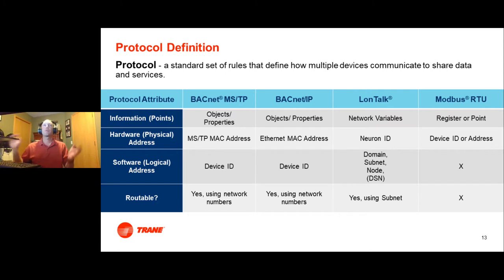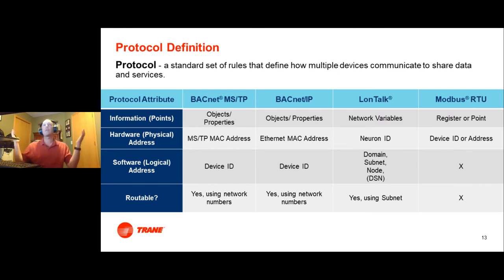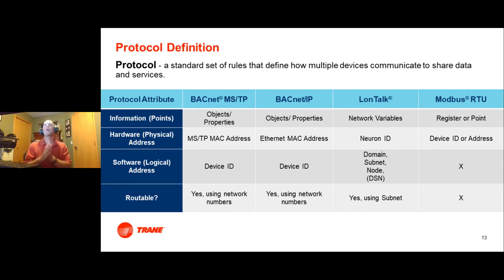A protocol, at a high level, is a way for two different controllers to communicate — hopefully between different vendors to help build our open system. Using a compressed version of the OSI seven-layer model, the really important thing when we talk about a BAS communications protocol is having a clear definition of the points, information, or data being shared. Every protocol may have a different name for it, but a good definition is critical, and that's what we can discuss as system integrators.